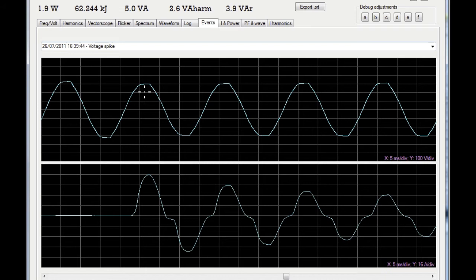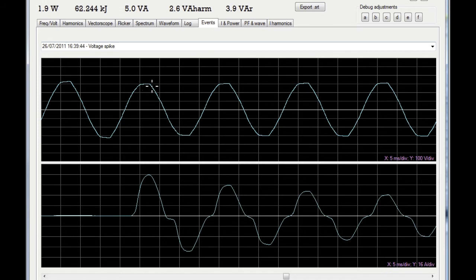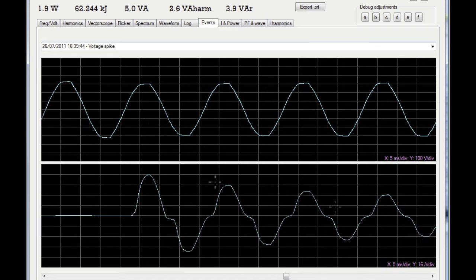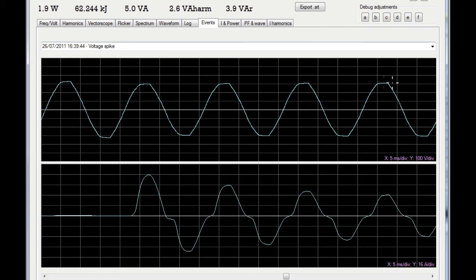As you can see, there is actually a big voltage dip here. 330 volts odd, down to under 300, probably about 299, 300 volts on that cycle where there's 64 amps being drawn. As the current goes down, you can see the voltage going back up again. So it's probably just under 310 volts there. 310 volts peak.